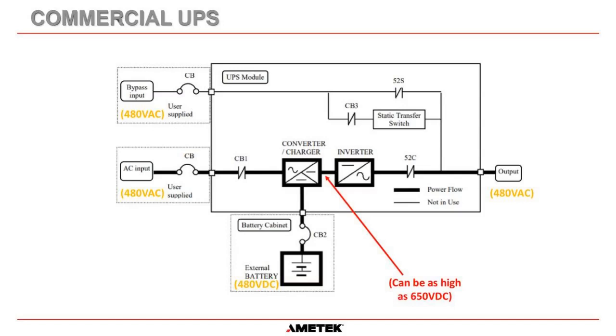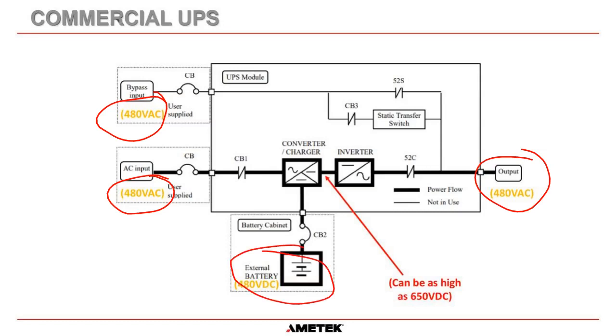We're going to start with what would be considered a normal commercial UPS, taken directly from a commercial UPS manufacturer's manual. The first thing you'll notice is that most commercial UPSs use three-phase 480 volts AC directly into the UPS itself, and the battery for this system is also 480 volts DC. There's a specific reason for that — it's down to Ohm's law: P equals VI.